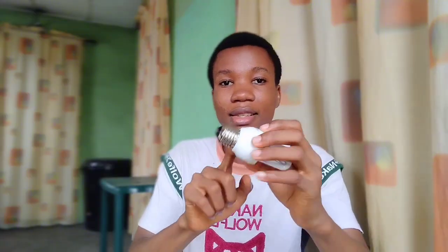Now you're going to be wondering, how does this actually work? It's the same thing as I said: there's a step-up transformer inside the ballast, which steps up the voltage to 600 volts. That excites the mercury inside the tube and generates ultraviolet light. That triggers the phosphor coating, which changes it to visible light.